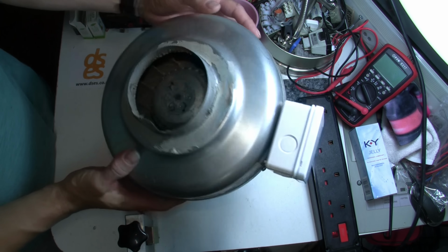Let's start with the relay, which has 8 terminal pins and consists of 2 separate double pole switches, each with a common terminal, a normally closed terminal and a normally open terminal. For those not familiar with relays, this is similar to the white plastic light switches I'm using here, but it's all contained within the relay housing. You can think of the normally open and normally closed terminals as L1 and L2 on a 2-way light switch.